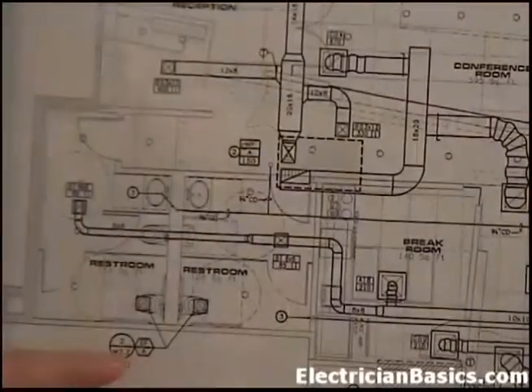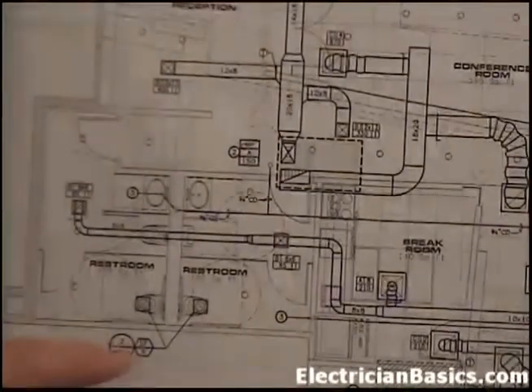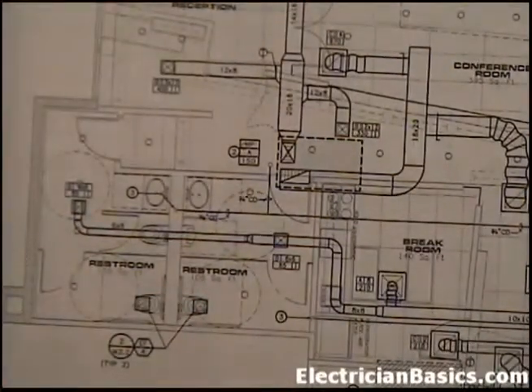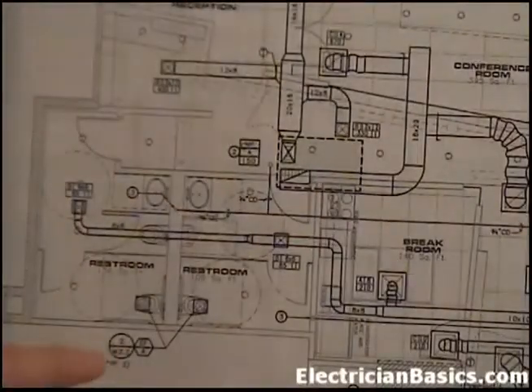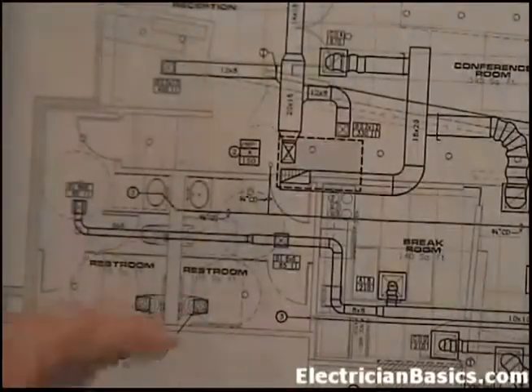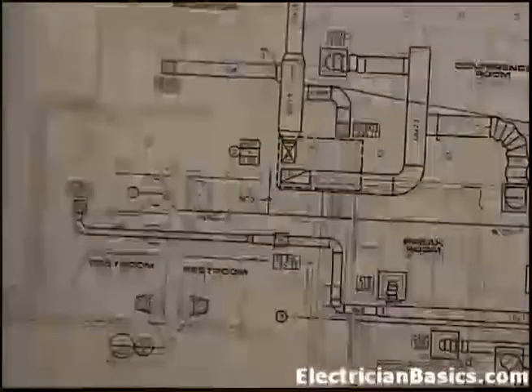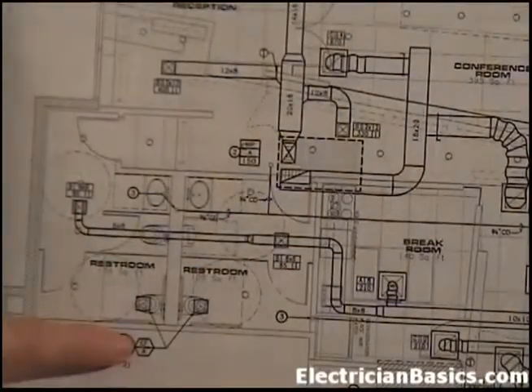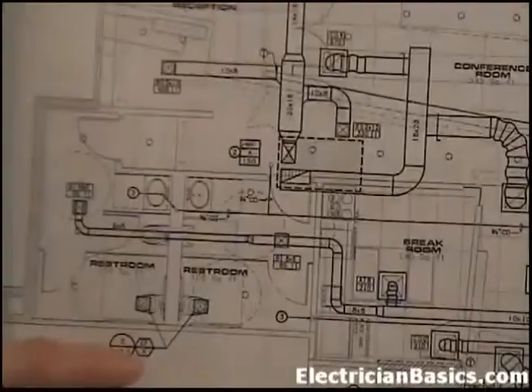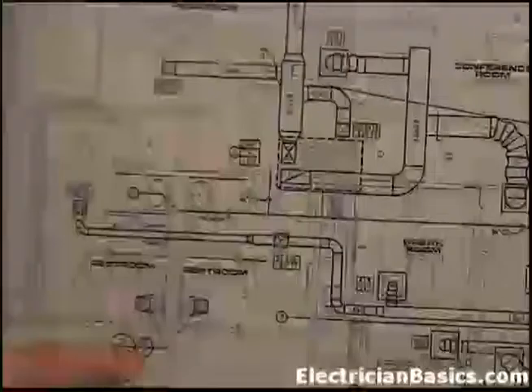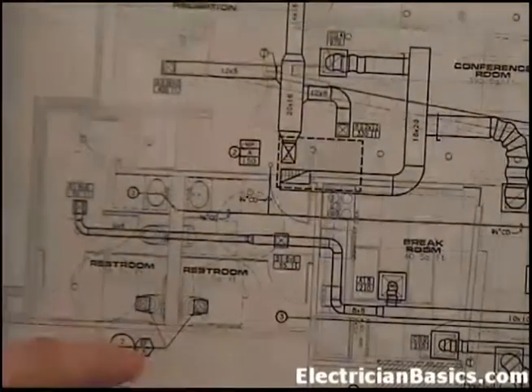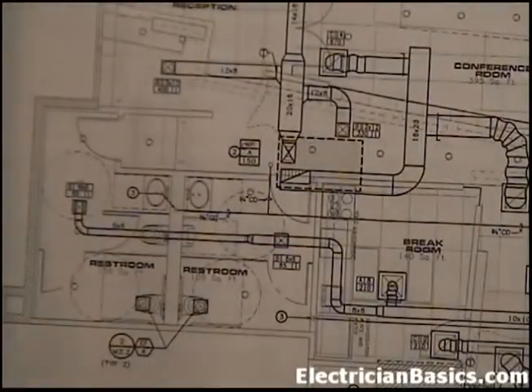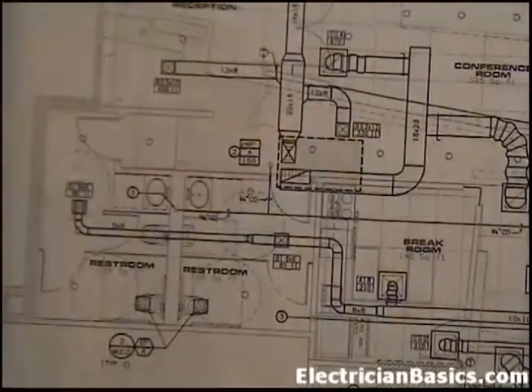If we look here, we have the circle that's split in half and the hexagon split in half, pointing to each of these two pieces of equipment. Now those are the exhaust fans in the bathroom. Both of these apply to each one of these pieces of equipment, so the circle and the hexagon both apply. Now if you remember the hexagon, the top half was the equipment, and EF stands for exhaust fan, and the bottom half is the schedule. So on Schedule A is where you find these exhaust fans. And since there's only one type of exhaust fan, that's going to be the only entry on that schedule. We talked about that on the last page.